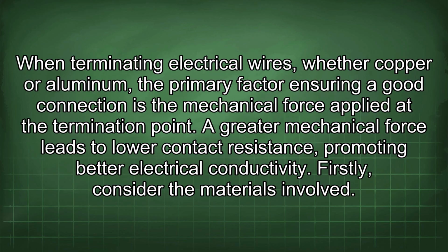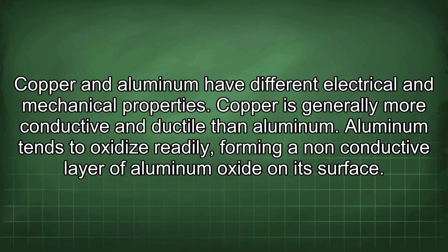When terminating electrical wires, whether copper or aluminum, the primary factor ensuring a good connection is the mechanical force applied at the termination point. A greater mechanical force leads to low contact resistance, promoting better electrical conductivity. Firstly, consider the materials involved. Copper and aluminum have different electrical and mechanical properties. Copper is generally more conductive and ductile than aluminum.